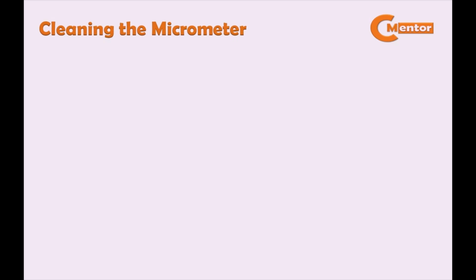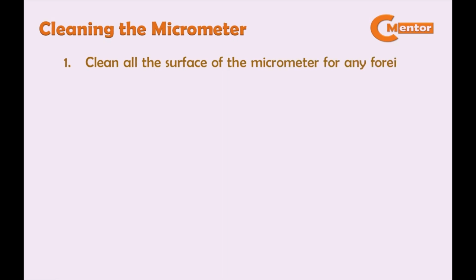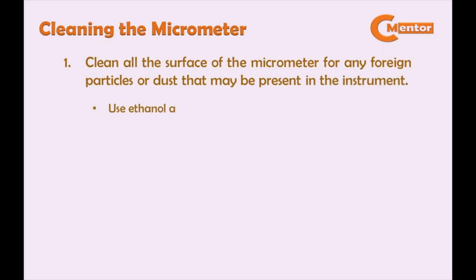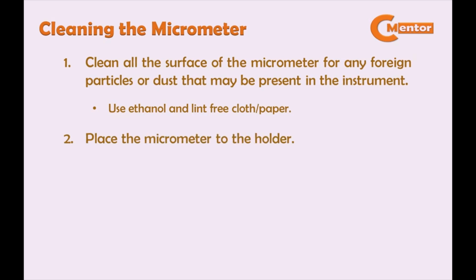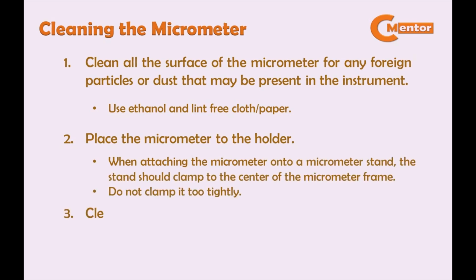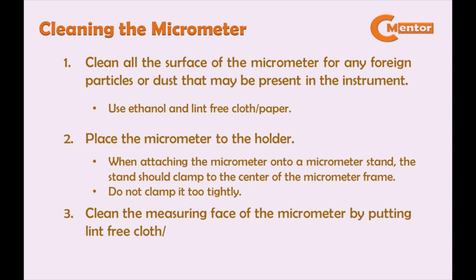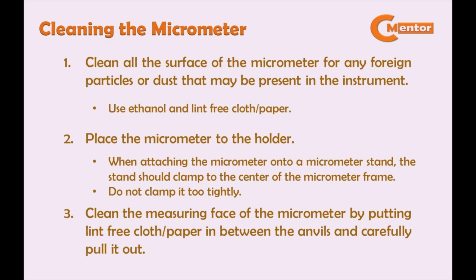Here is the procedure on how to clean the micrometer. First, clean all the surfaces of the micrometer of any foreign particles or dust that may be present on the instrument. Use ethanol and lint-free cloth or paper. Second, place the micrometer in the holder. When attaching the micrometer onto the micrometer stand, the stand should be clamped to the center of the micrometer frame. Do not clamp it too tightly. Third, clean the measuring face of the micrometer by putting lint-free cloth or paper in between the anvils and carefully pulling it out. Here is the sample video on how to clean the micrometer.